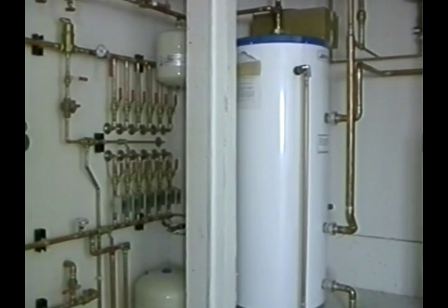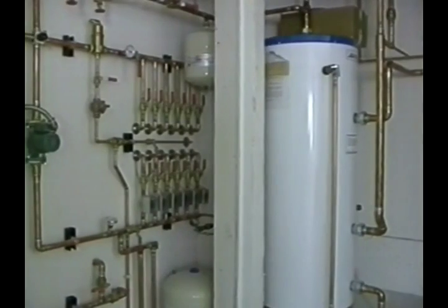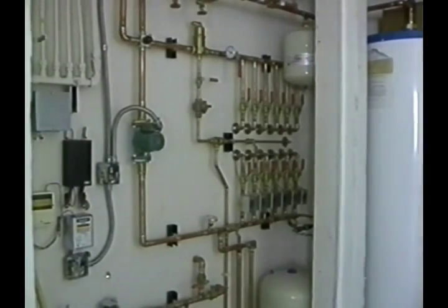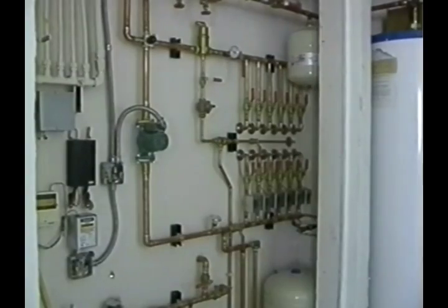When you choose a hot water heat system, there are various uses for the system. An abundance of domestic hot water can be provided using an indirect tank. This water heater is basically a heat exchanger that provides domestic hot water using the boiler's 180-degree water as its heat source.